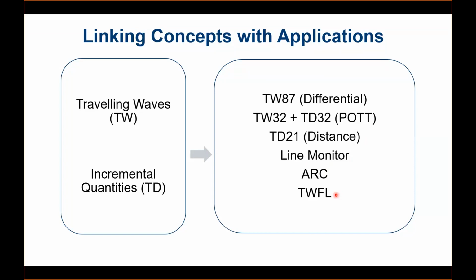We have a traveling wave fault locator, which is much more precise than the conventional distance or impedance-based methods. It can identify faults to within one tower span, that is, plus or minus 300 meters. These are very crucial benefits you get from traveling waves and incremental quantities in terms of security, sensitivity, speed, and fault location as well. It will save a lot of cost on line monitoring. You can avoid outages if you have a preventive maintenance schedule for a line that has a problem or a potential problem. So you can save a lot of money and expenses on outages, and for fault location, you don't need to patrol as much of the line.